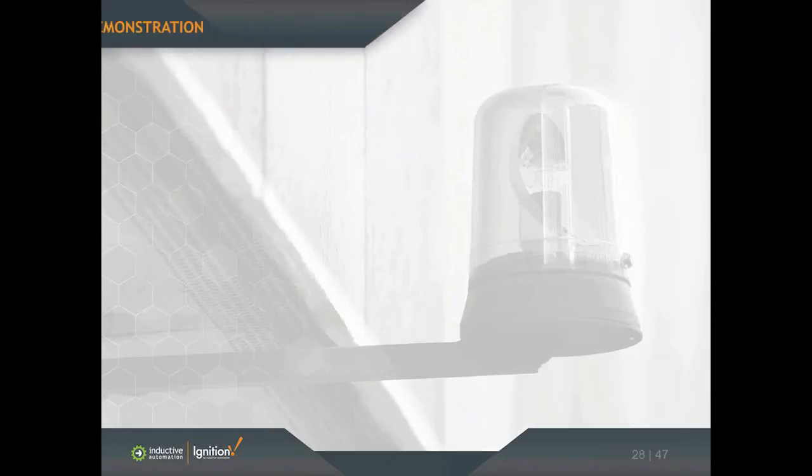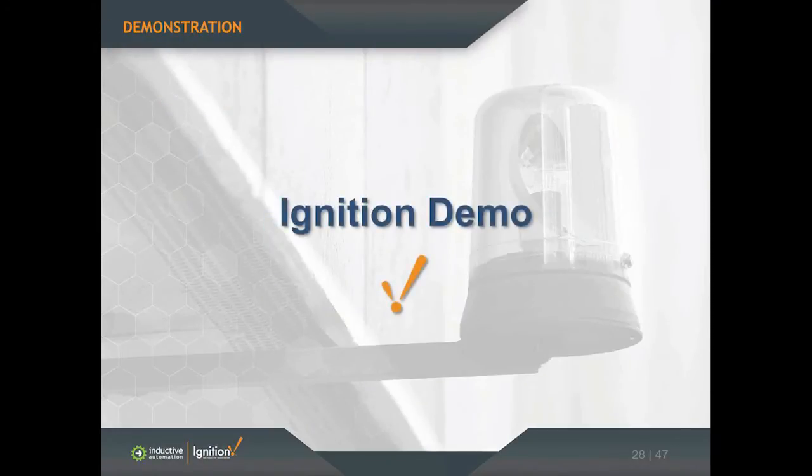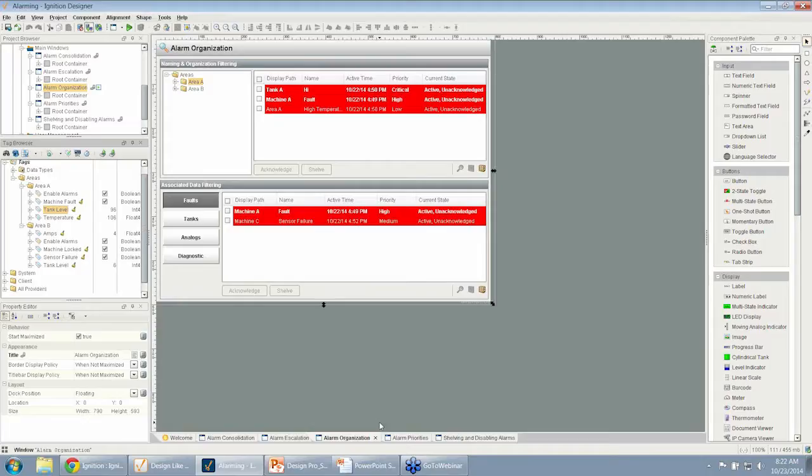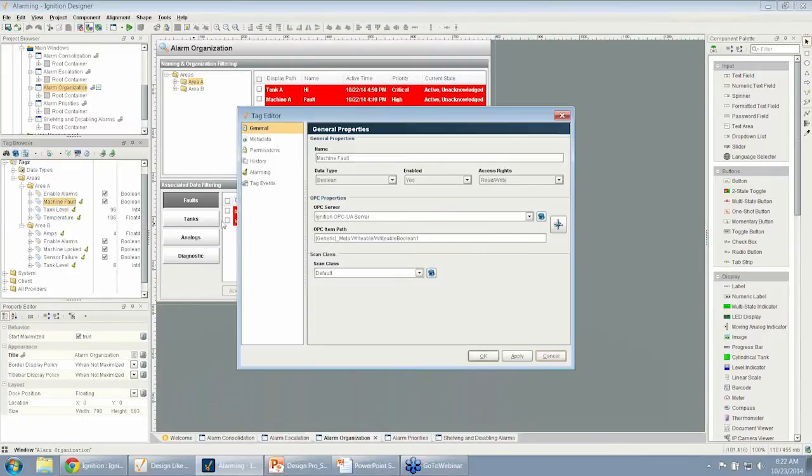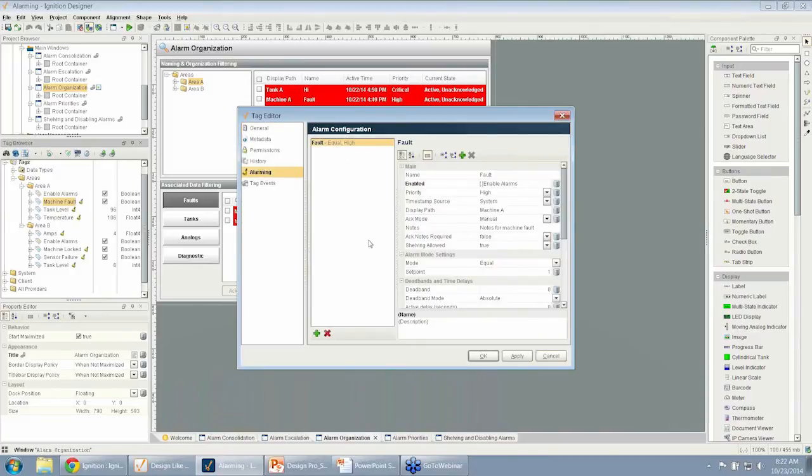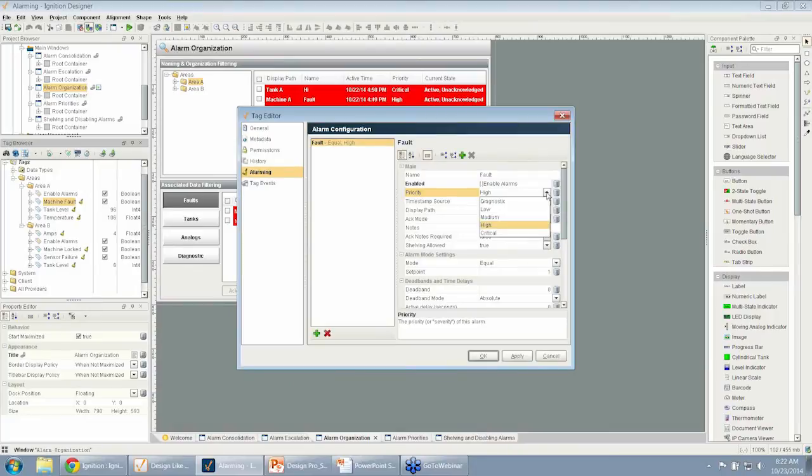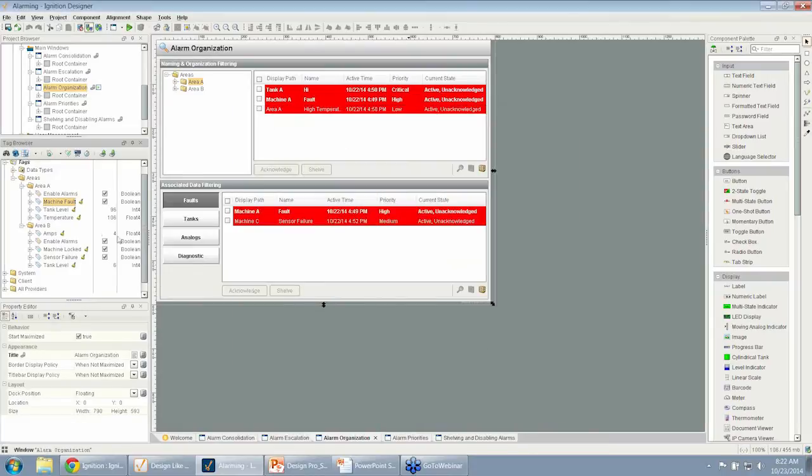I want to show another demonstration about the priorities of alarms in Ignition, how they can get set up, and how we can use those on screens. I'm going to go back to the designer. On a particular tag, say if I go to my machine fault and look at that alarm, I can see at the top there is a priority from diagnostic all the way to critical. On this machine fault, I've given it a high priority.